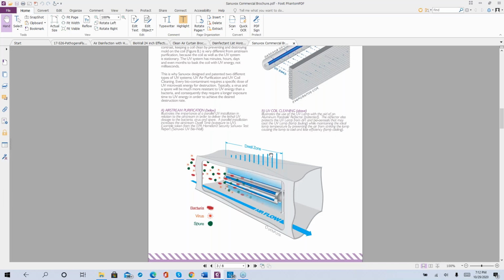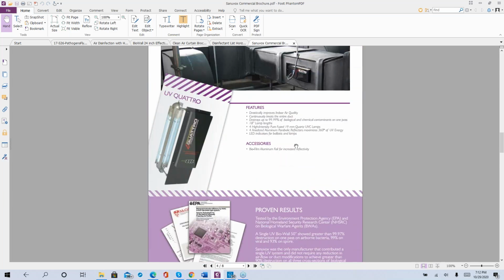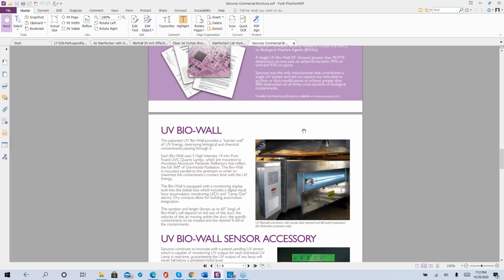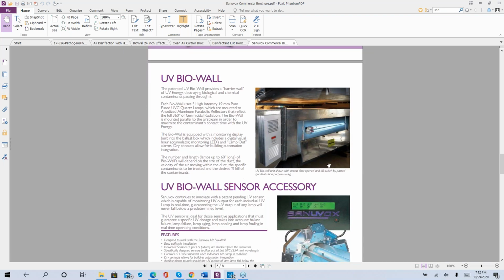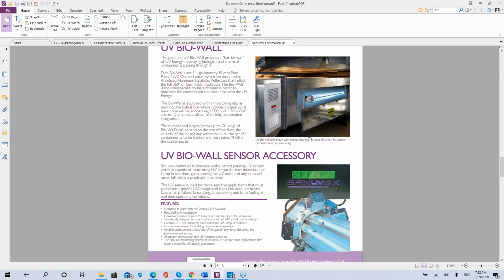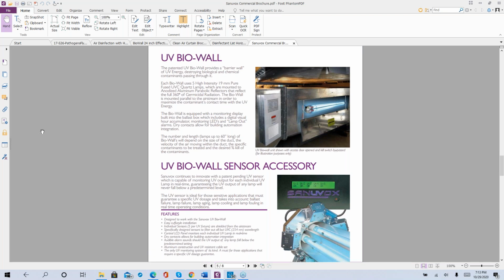Question while you're doing that, Paul, is dwell time. So you need enough dwell time, which means you need the air to be in the residence of this light for a long enough period of time to kill. Velocity, therefore, is really important. It has to be long enough. And that implies that you have to have enough straight duct space to be able to insert this guy into, right? That is correct. And although everybody always tries to get away from turbulence, turbulence here is good.